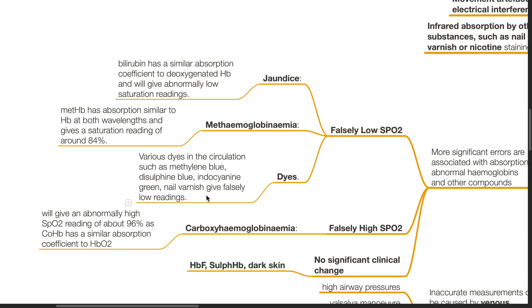In the presence of carboxyhemoglobin, this will give an abnormally high SpO2 reading of about 96% as carboxyhemoglobin has a similar absorption coefficient to oxygenated hemoglobin.